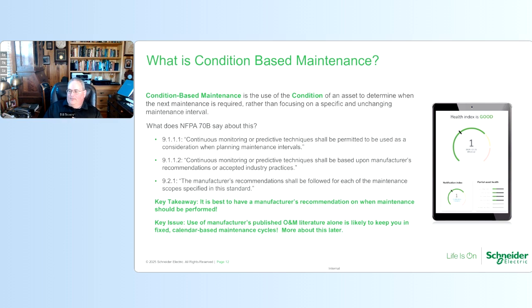So some things from NFPA 70B. Section 9.1.1.1 permits continuous monitoring or predictive techniques to be used as a consideration when planning maintenance intervals. 9.1.1.2 requires continuous monitoring or predictive techniques to be based upon manufacturers' recommendations or accepted industry practices. And Section 9.2.1 requires that the manufacturer's recommendations be followed for each of the maintenance scopes described in the standard. So a key takeaway here is that it's really best to have a manufacturer's recommendation for when maintenance should be performed and what maintenance should be performed.